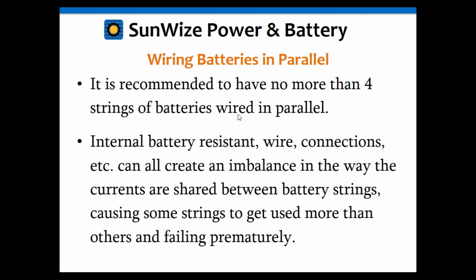Let's say you're trying to use 100 amp hour batteries in a 12-volt system, and once you have 4 of those in parallel, you're up to 400 amp hours, but you really need 600 amp hours. Maybe at that point you should go up from a group 27 battery to either a group 4D or 8D, where 2 of the 8Ds in parallel would give you around 500 to 600 amp hours. That gets you closer to what you need with only 2 strings instead of having to go to 5 or 6. So we usually recommend going to a bigger battery at that point to minimize wiring batteries in parallel.